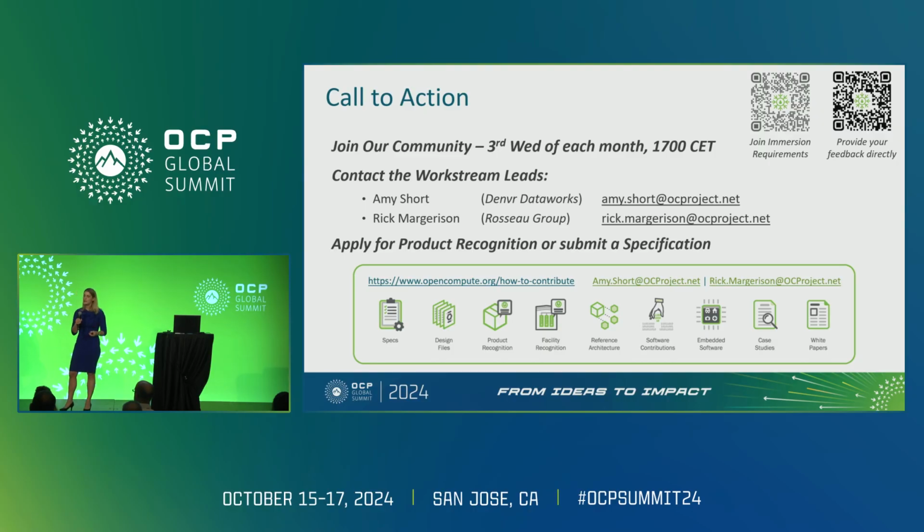What I'll also say is that the requirements document is intended to be a very practical baseline foundational description of how products should actually perform or features of the products to actually ensure good function and safety. And so they're not intended to be overly restrictive. We don't want to define for the environment and the ecosystem what they have to actually deliver. So that's where feedback, I think, from those support communities can help us to understand with granularity what should the flashpoint be. What is the data basis for the restriction that we want to apply to flashpoint? What should the viscosity be? Should we worry about dielectric properties of the fluid? Are there safeguards that we maybe haven't thought of?